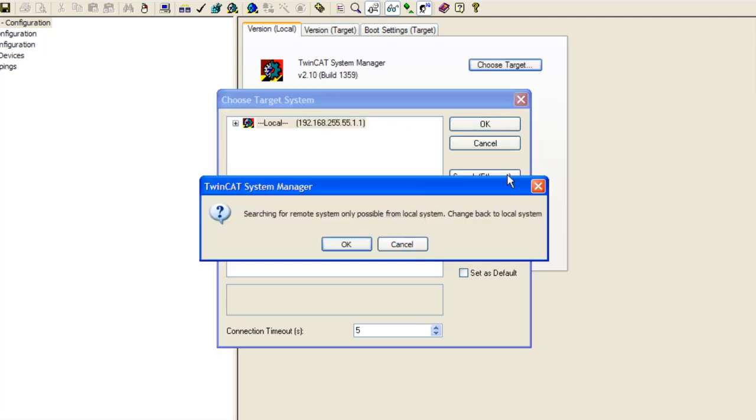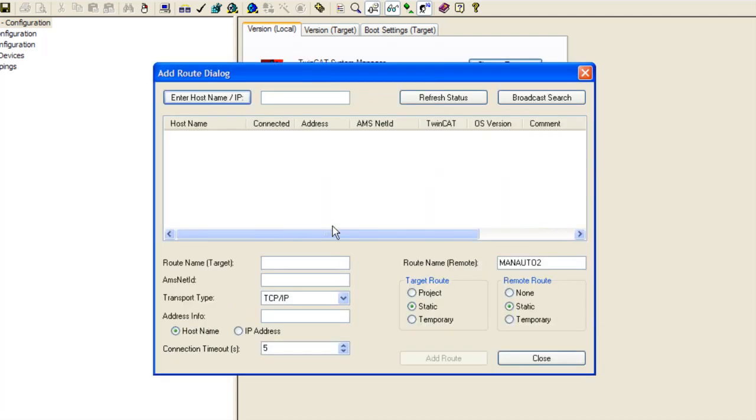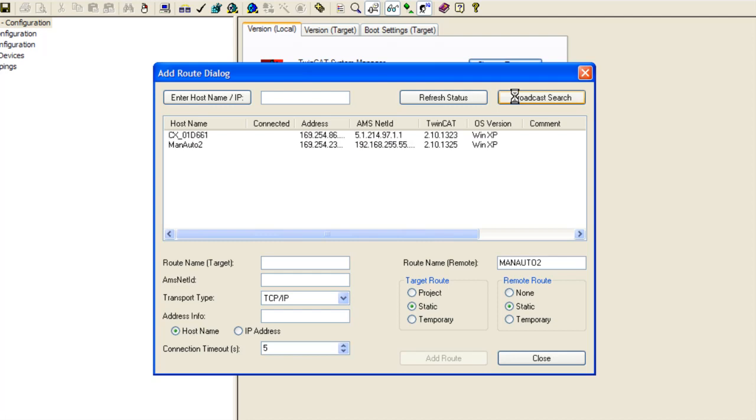And click the search Ethernet button. Now if you get this message it just says searching for remote system only possible from local system, just click OK to that because we want to get to the add route dialogue. Now once we get to the add route dialogue we are going to click broadcast search. What that does is basically send messages out over the network looking for any instances of the TwinCAT PLC runtime.